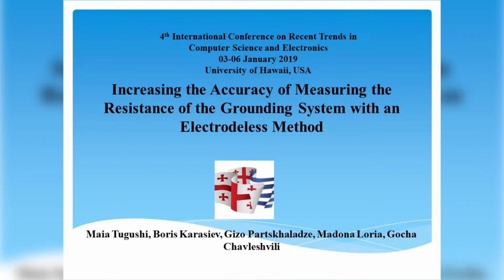Topic of experiment: increasing the accuracy of measuring the resistance of the ground system with an electrodeless method. Recently, electrodeless methods of measuring the resistance of grounding devices have appeared, with the help of special clamps, but a large methodological error limits the possibility of their use, especially when rationing low resistances. The article shows the possibility to improve the accuracy of electrodeless measurement methods using commercially available measuring instruments.